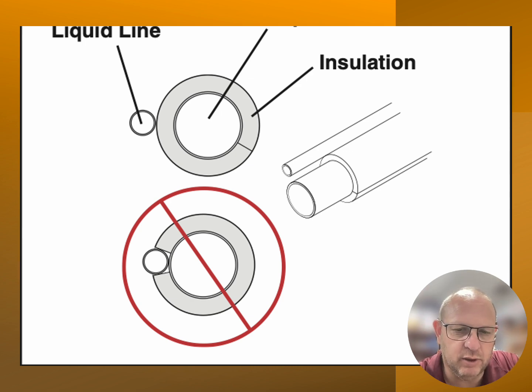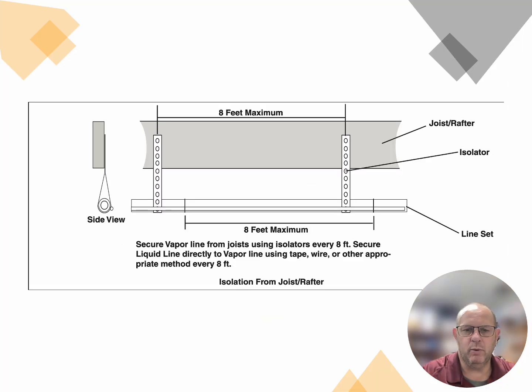When we go into supporting our actual line set, I suggest you use some sort of plastic hanger, so it doesn't eat its way through that copper. You're going to want to do that a maximum of 8 feet, but I would like to see it closer together, every 5 feet or so on that line set, so it's not drooping. It must be run in such a way where the suction line is going to be pitched towards the outdoor unit so that oil can return to that outdoor unit so we don't lose compressors due to that. But secure the vapor line from the joist using isolation or strapping or some other form of vibration elimination to keep that line set from transferring noise inside of the building itself.